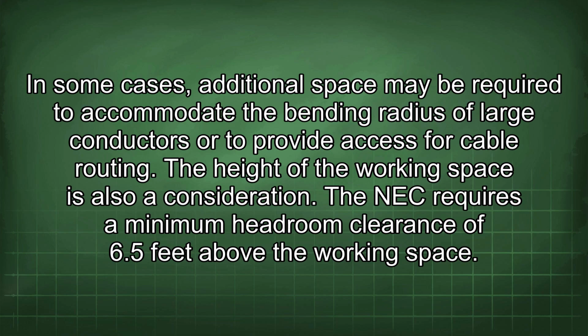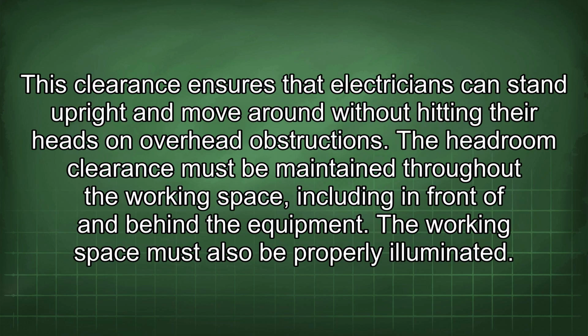The height of the working space is also a consideration. The NEC requires a minimum headroom clearance of 6.5 feet above the working space. This clearance ensures that electricians can stand upright and move around without hitting their heads on overhead obstructions. The headroom clearance must be maintained throughout the working space, including in front of and behind the equipment.